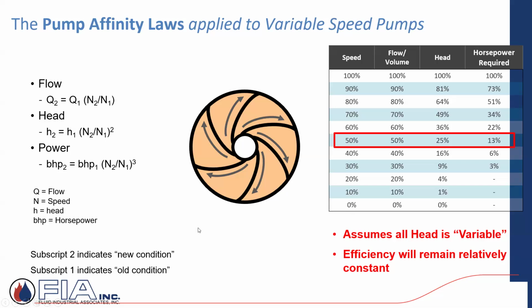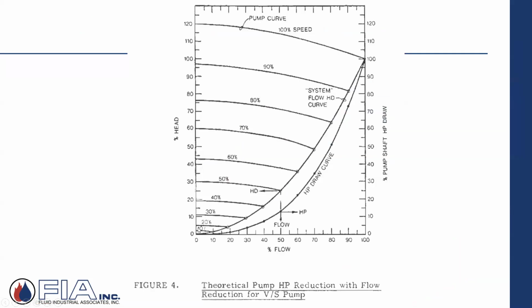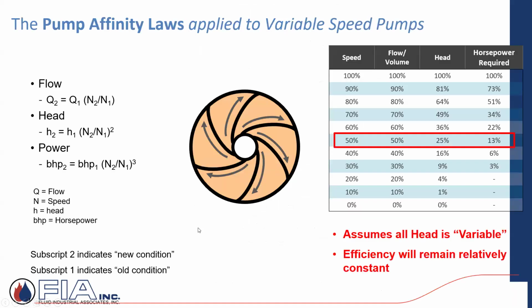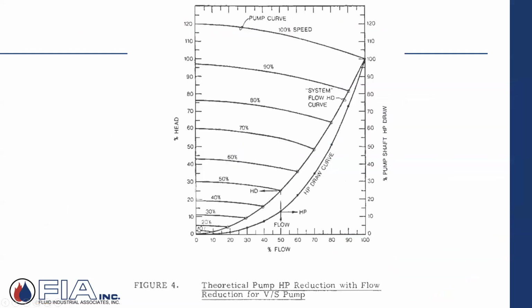So cut the flow in half. Head loss is a quarter, and the required horsepower is about 13%. So it's pretty substantial, and that's where the savings comes in. This would have been reflected, again, in one of your manuals, and it was showing the same thing in graph form that this table shows right here. You take that 100% of flow rate, you reduce it by about 50% over here. The corresponding head loss is 25%, and the corresponding required horsepower is just under 15. It's about 13%.